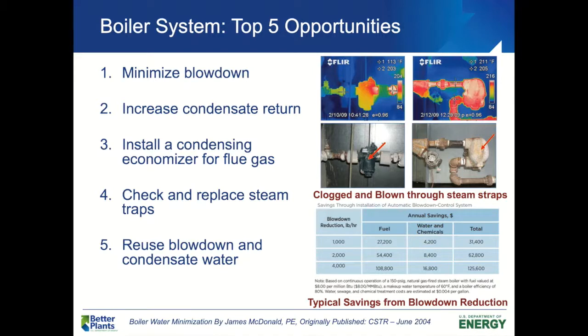So this is a capital intensive project. What a condensing economizer does is very similar to a typical sensible heat economizer, which just captures the excess heat from flue gases. The condensing economizer takes it one step further and captures the latent heat associated with that as well. And in that process, some of the water vapor is also recovered, saving on water.